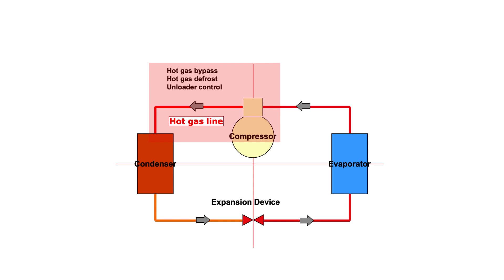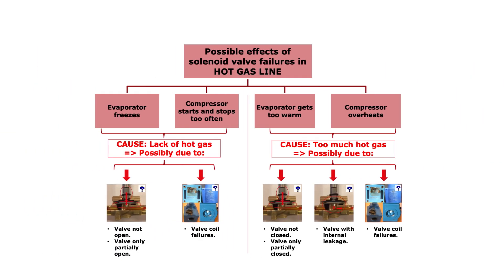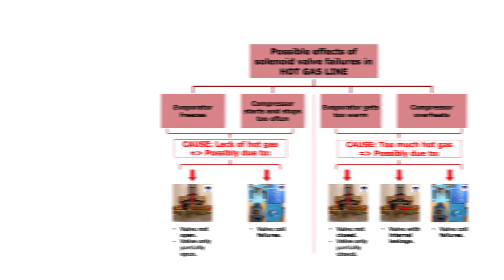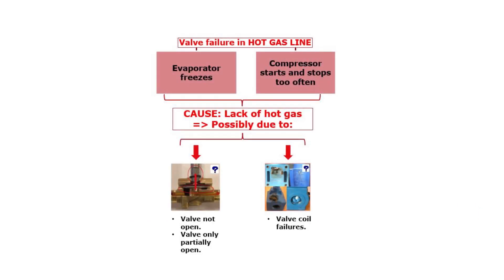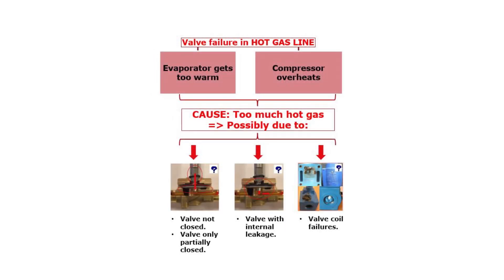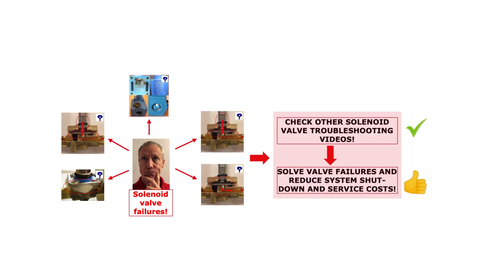Looking at the hot gas line as illustrated here, you normally use solenoid valves for hot gas bypass, hot gas defrost, and unloader control. Here you see an overview of how possible solenoid valve failures might affect the refrigeration system when the valve is located in the hot gas line. The evaporator freezes and or compressor starts and stops too often — caused by lack of hot gas due to the valve not opening or only being partially open, or the valve coil is not working correctly. The evaporator gets too warm and or compressor overheats — caused by too much hot gas due to the valve not closing or only being partially closed, the valve is internally leaking, or the valve coil is not working correctly. Check out the other online solenoid valve troubleshooting videos to get more details and how to solve them to efficiently reduce system shutdown and service costs.